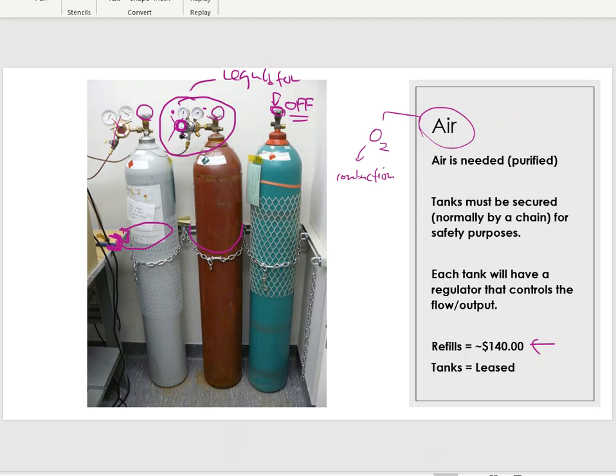A $140 air tank will last us a couple of months if running normally, but we only run our TOC when needed — typically a few months a year — so we usually get a refill once a year. In a high-throughput analytical laboratory, however, a tank might only last a week before needing replacement or a backup tank switched over.